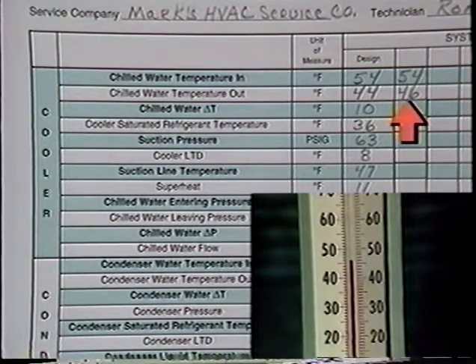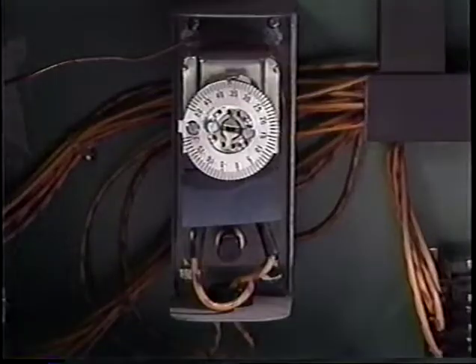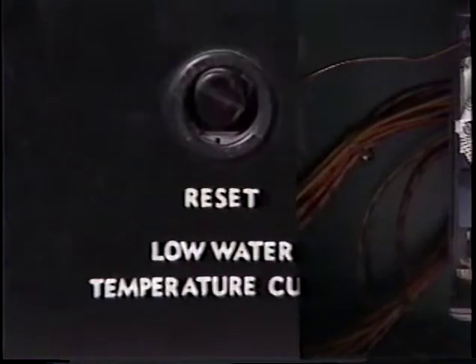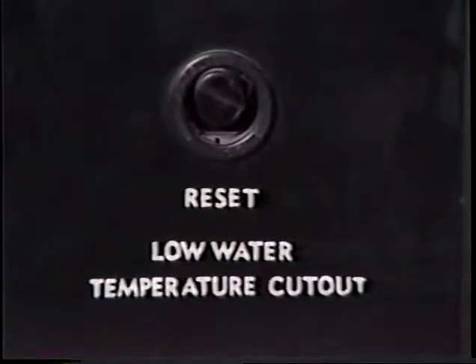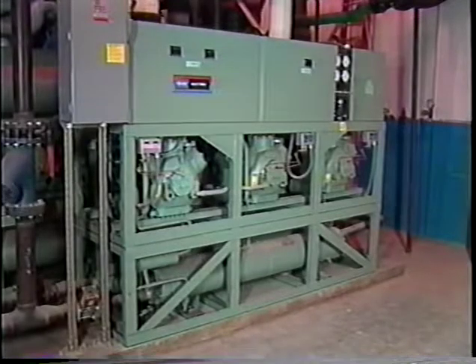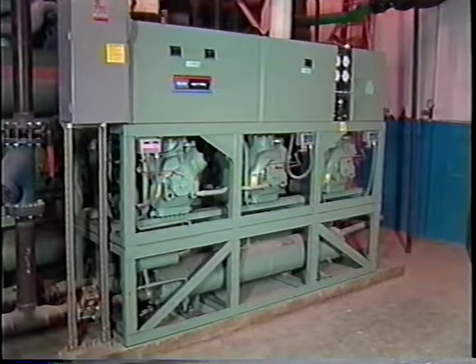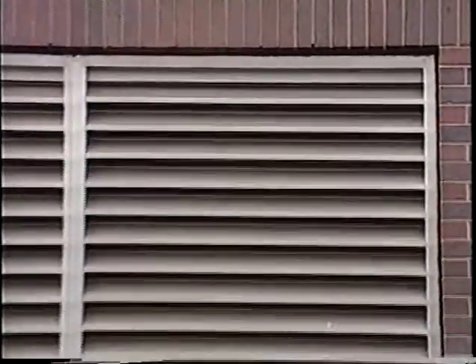Under extreme light load operation, this temperature could drop below design leaving temperature. However, a control sensing the water temperature, a low water temperature cutout recycle switch, will shut the machine down. It's not economical or good operating practice to operate a chiller under extreme light load conditions if other means, such as outside air, will accomplish the cooling job.